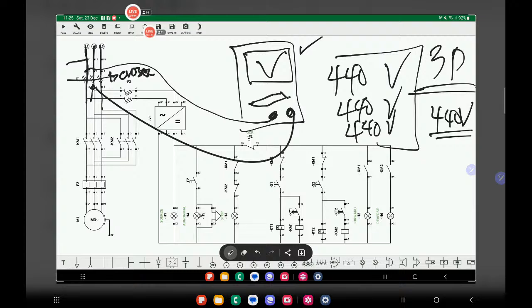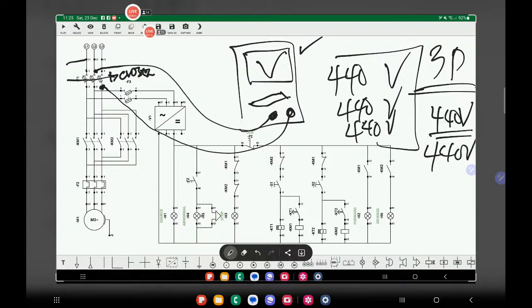In this way, it would be very easy for you to just move the probe again. Let's say line 1, and the next probe will be on line 3. I should be having 440 volts also. Then I'll move the first onto number 3, and I should be having 440 volts. If with this technique you have all 440 volts in the system, that only means you're not having a single phasing, so all the phases and all the contacts of your F1 are in good condition.